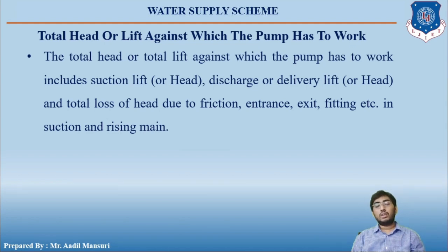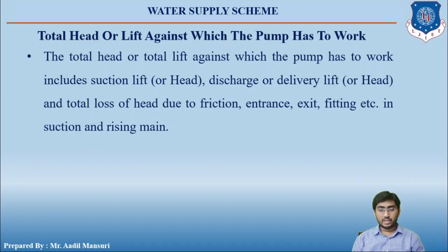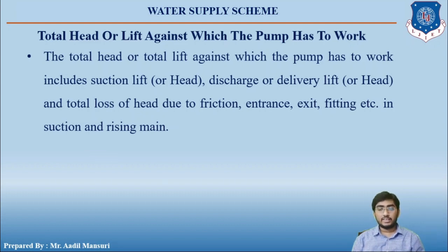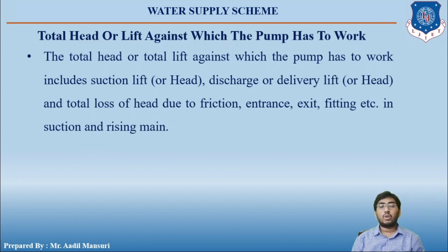The total head or lift against which the pump has to work includes: suction lift or head, discharge or delivery lift or head, and the total loss of head due to friction, entrance, exit, fittings, etc. in the suction and rising main. So you need to find out how much head is suction, how much is discharge, and also the losses that occur in the pipe during transmission.